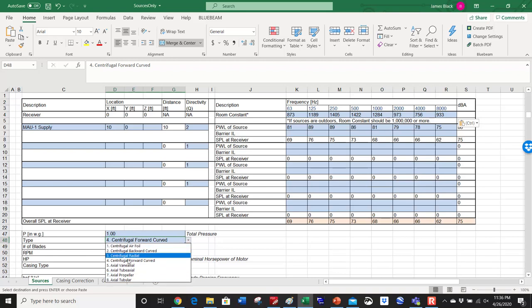And then we have the type of fan. There's a bunch of different fans here. This centrifugal forward curved is a pretty common one. Then number of blades. A Sirocco fan is a pretty common one. It can be fairly hard to find the exact number of blades, but the Sirocco one is fairly common, and I use that a lot of the time if I can't find better data. Then RPMs, a lot of the time 1600 RPM, but that might change.